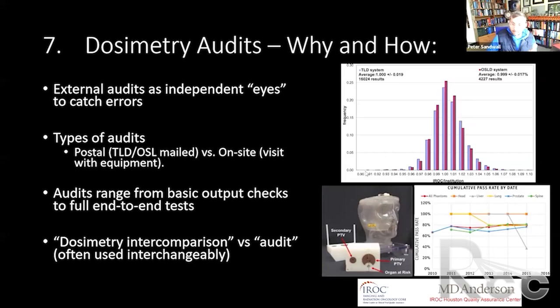And so, as we mentioned earlier, 10% is significant enough to be noticed. The physicians are not going to get the cure rates they expect. And in the case of 10% high, they're going to get increased toxicity. So this has very real impacts to patients. This cumulative pass rate by date shows pass rates for these end-to-end tests. And you can see there's all phantoms. They get about an 80% pass rate. The head, they get about 100%, or mostly 100% pass rate.